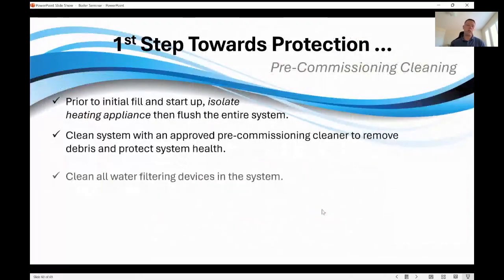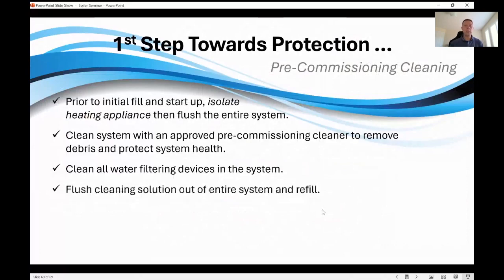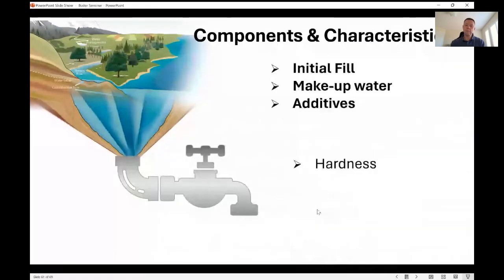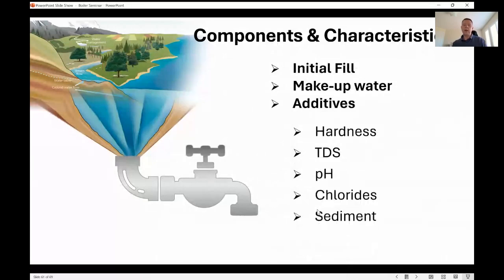So you always want to make sure you have quality water going in there. Prior to your initial fill, I would say isolate that heating appliance and flush your system out. Clean the system with an approved pre-commissioning cleaner to remove any debris. Clean all your water filtering devices. Any of the crap that somehow is in there can get dislodged, and flush the cleaning solution out of the entire system and refill it. Very important. For your initial fill, you want to make sure your makeup water is treated and you have good water coming into it, not just city water coming in, because if there's a leak, you're going to potentially lime it up.